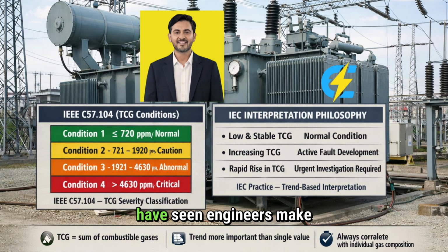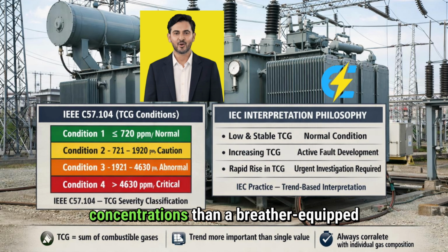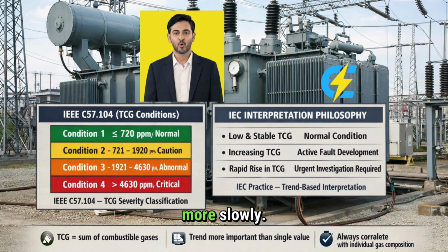In the field, I have seen engineers make the mistake of focusing solely on TCG values without considering the broader context. Remember that factors like transformer design, oil volume, operating temperature, and even the presence of oil additives can influence TCG levels. A sealed transformer will naturally have higher gas concentrations than a breather-equipped unit because gases escape more slowly.